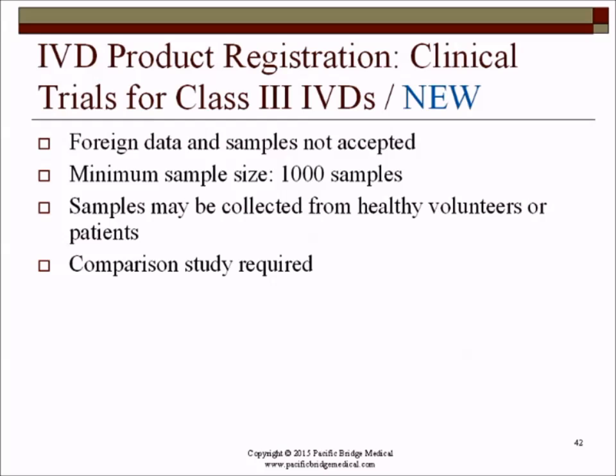So the minimum sample size is 1,000. Samples may be collected from healthy volunteers or from patients. And then the main thing here is a comparison study is required to get your Class 2 or 3 IVD approved in China. So similar to a drug, the IVDs require a comparison method to get approval in China. And if you can't do a comparison method for your IVD, it's going to be very difficult to get approval, and there's really no way to calculate the accuracy for the new IVD.